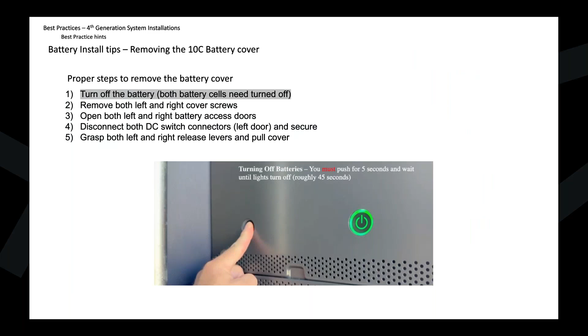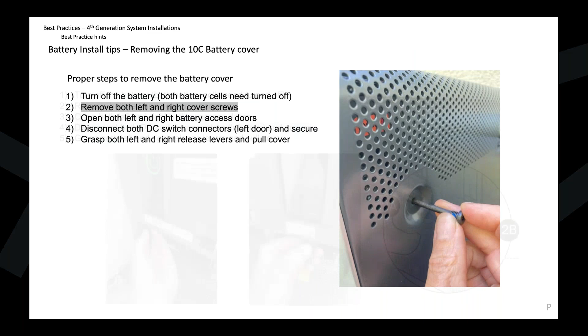Once you power down the battery cells, there are right and left screws on the cover, up on the front side, upper left and upper right. Go ahead and get those off. Then we need access to the bottom left and bottom right of the battery. This is why it's important to give yourself ample room, especially with multiple batteries installed—a good 8 to 10 inches between batteries so you can access the switches and the doors. We don't want them so tight you can't open the doors and have workable space.